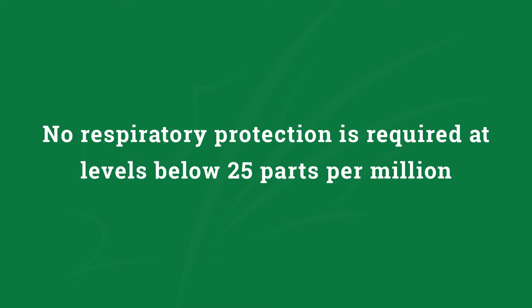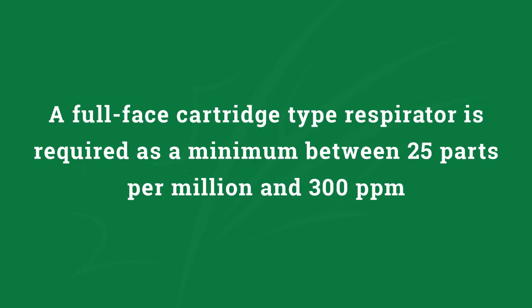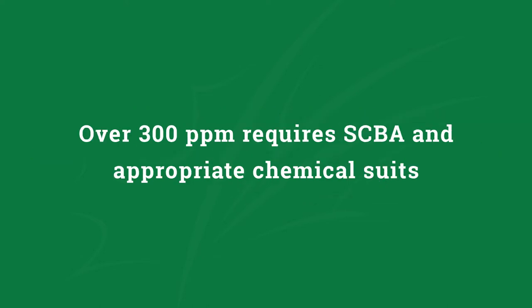In summary, no respiratory protection is required at levels below 25 parts per million of anhydrous ammonia. A full-face cartridge type respirator is required as a minimum between 25 and 300 parts per million. Supplied air respiratory protection is required over 300 parts per million, together with chemical suits appropriate for the situation. Note that in general, any filtering respirators may only be used when oxygen is greater than 19.5%; if not, a self-contained breathing apparatus must be used.